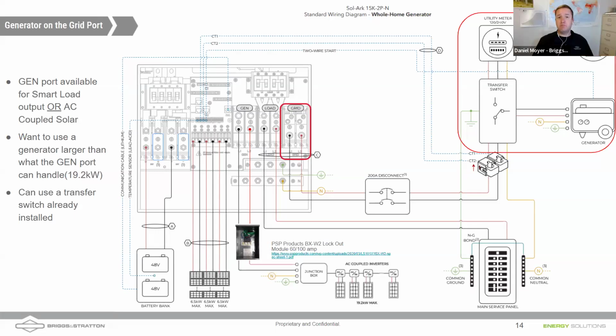You mentioned it's usually uncommon, right? If the AC solar is producing, that means it's charging the batteries, and there should be no reason that generator is coming on. But perhaps it's early morning, or a cloud passes over. Yeah, absolutely, so those are the conditions you're worried about, right? The generator started because the batteries got a little low, and all of a sudden the cloud cover passes, it gets sunny out, the generator is running, and now there's excess solar trying to backfeed the generator because the battery state of charge was below that generator start point. And once that generator starts, it will run until those batteries are fully charged. That two-wire signal to start doesn't just cut off as soon as the AC coupled solar is there.